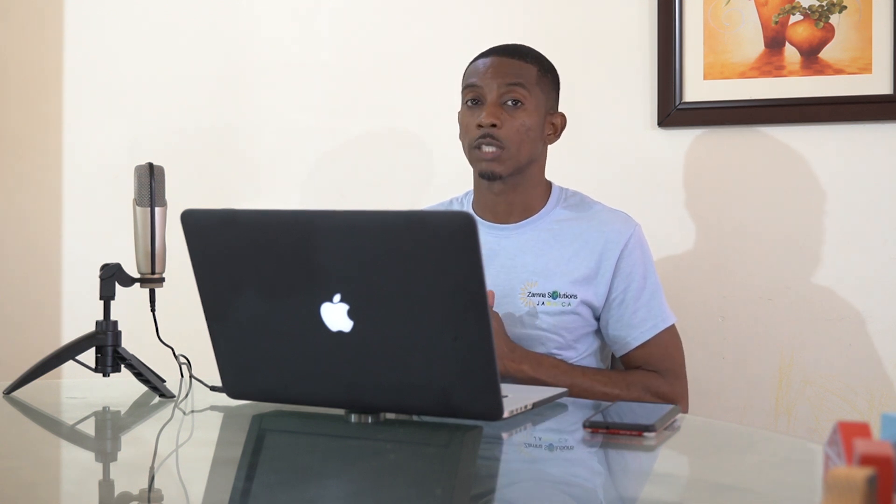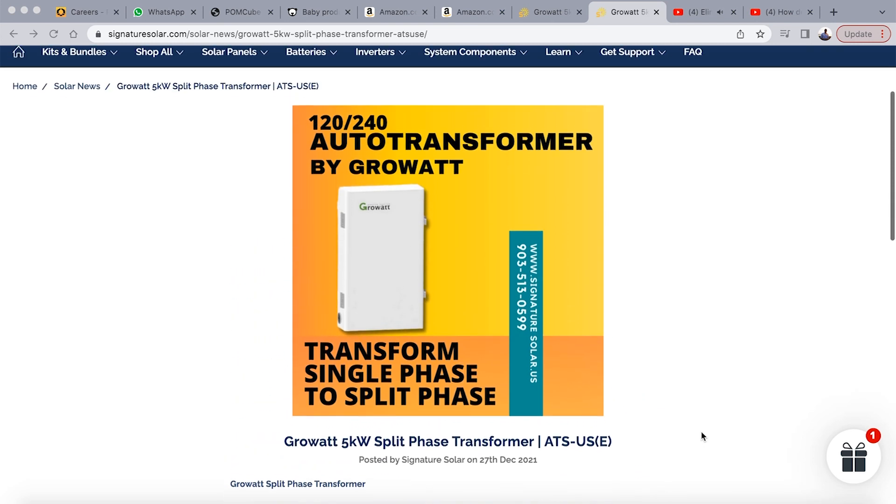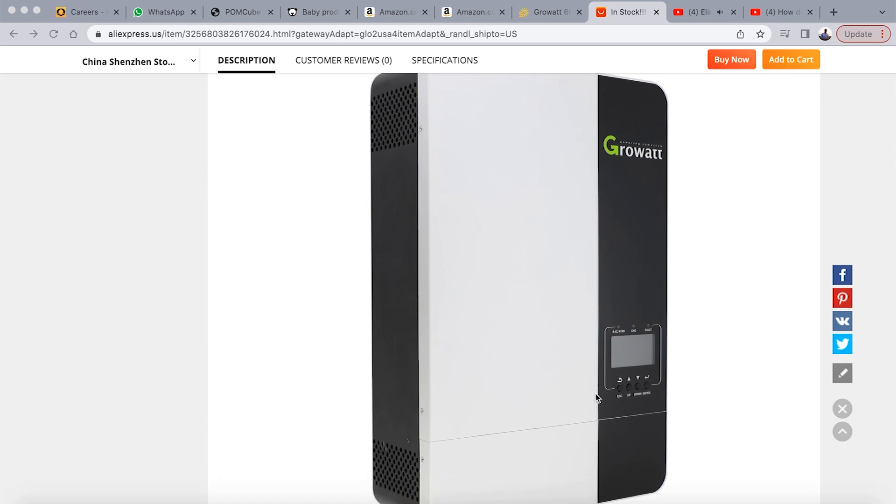One thing I forgot to mention: if you have already purchased an inverter and it only outputs 240 volts, what you're going to need to do is add another device — a split phase transformer — that will give you the ability to have your 110 and 220 volt appliances working. It's a split phase transformer by Growatt, and I'll link that in the description. Keep in mind that adding a transformer adds another device that may bring losses and another point of failure. So if you haven't yet bought the inverter, go search for one that's split phase and stackable. If you have already purchased, check out the transformer for a split phase setup — it's in the description.